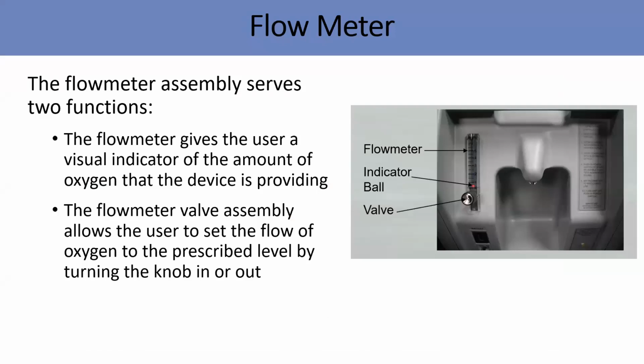Flowmeter, everyone knows, is at the front part of your oxygen concentrator. The flowmeter controls the flow. So you got 0 to 5 liters, some 8 liters, depending on the design and the brand. So these indicate how much flow is going through to the patient, all that. The ball is going to float in the system when you do some setting on the valve.